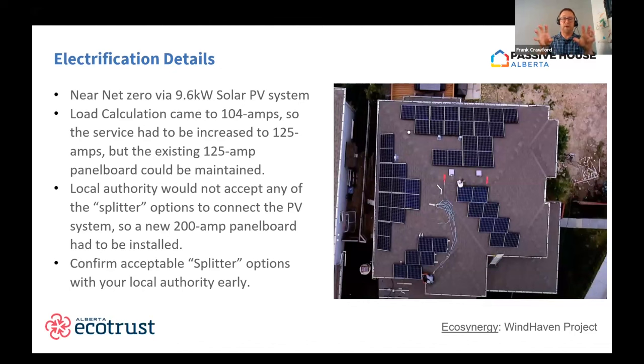So this is a good example of: do that peak load calculation before you start doing work to make sure you're under that 100 amps, and make sure you talk to your local jurisdiction to make sure you pick a splitter that is acceptable.